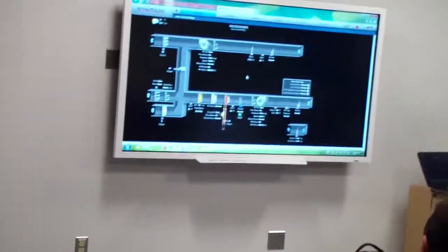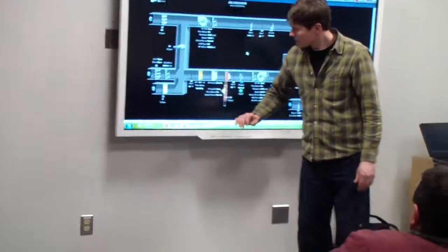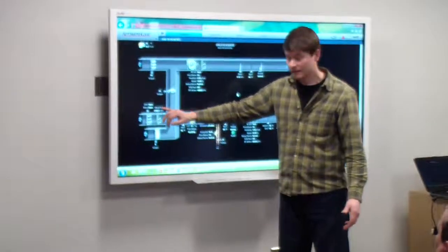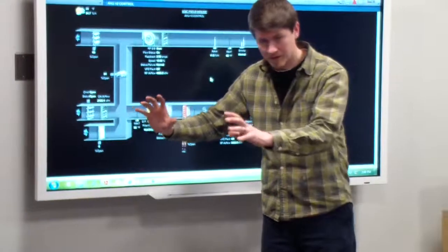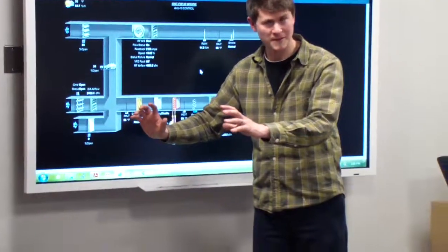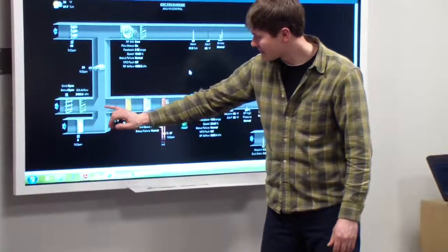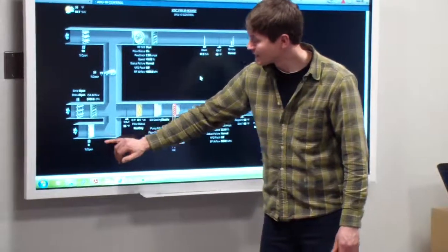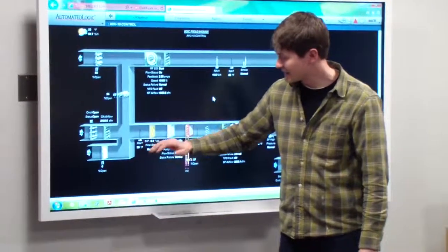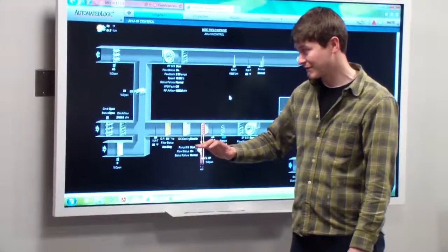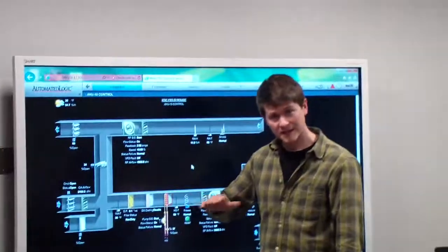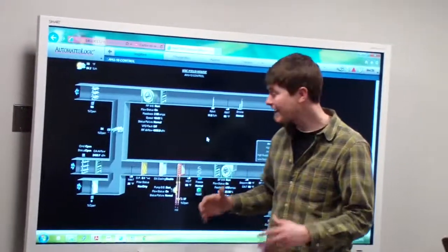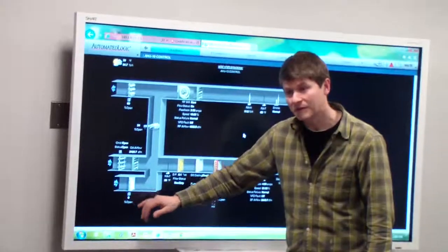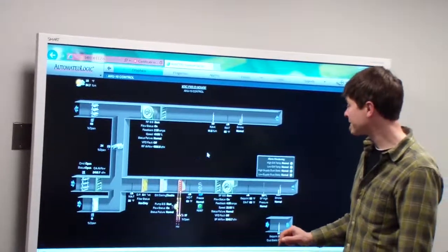And AHU-10, which we looked at once already. So you've got your minimum outside air damper, which has the flow station to monitor what's coming in. And then you've got your other 2 sections, which are set up right next to it. And we'll take a look at this when we go upstairs at the unit. This comes in based off of what this temp is. So this doesn't open if this starts seeing below a certain temp, which I believe is 45 degrees. Once it starts seeing 45, in order to protect everything that's in there, it starts closing off these 2 to make sure that we don't have any problems.